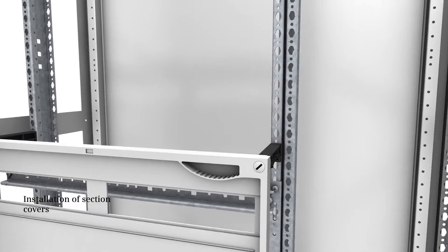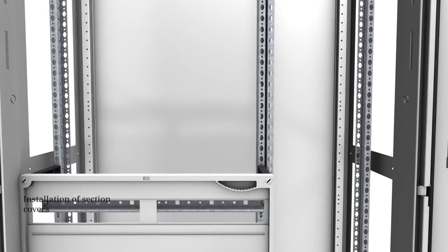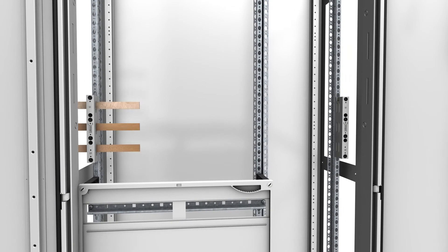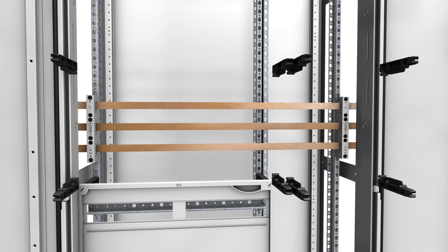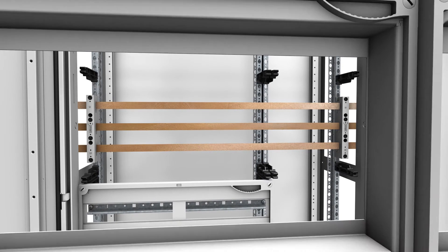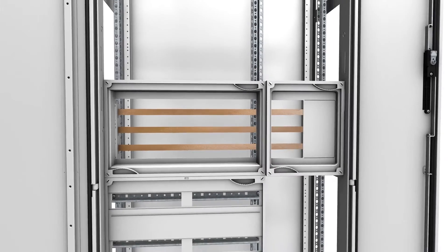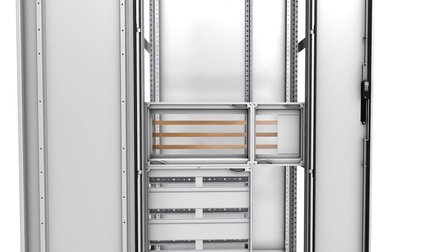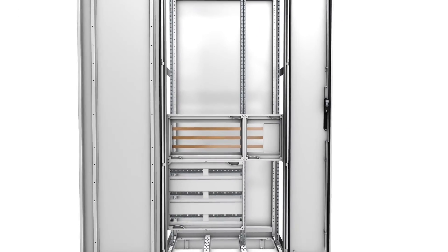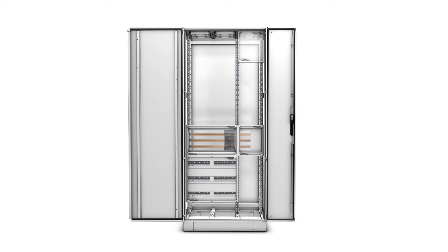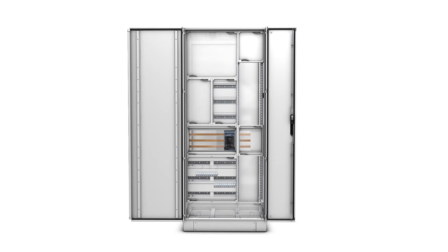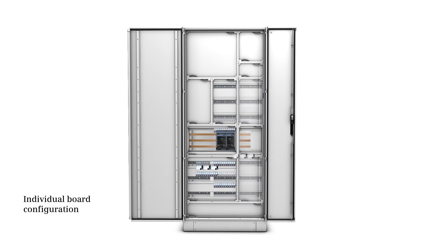The bus bar support position facilitates the installation of 40 millimeter and 60 millimeter bus bar systems. With the 8U bus bar system, various switching devices can be mounted easily, rapidly, and flexibly — a basic prerequisite for individual board configuration.